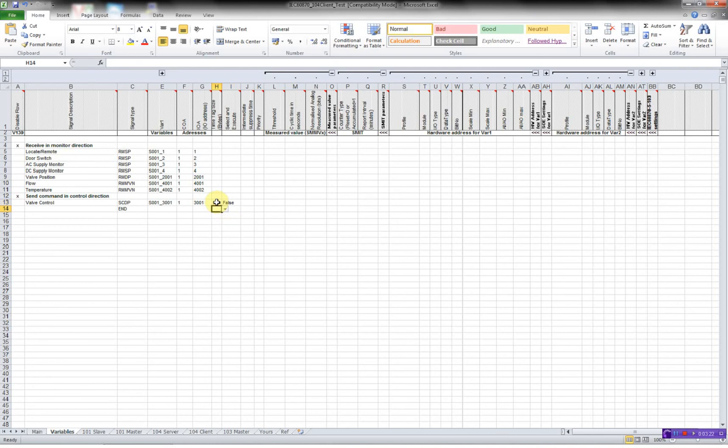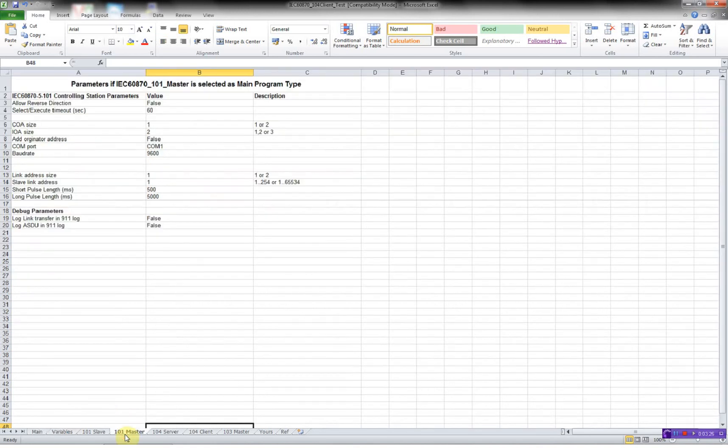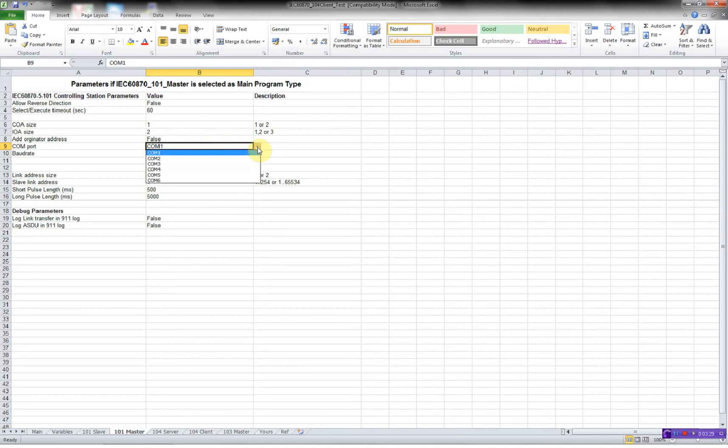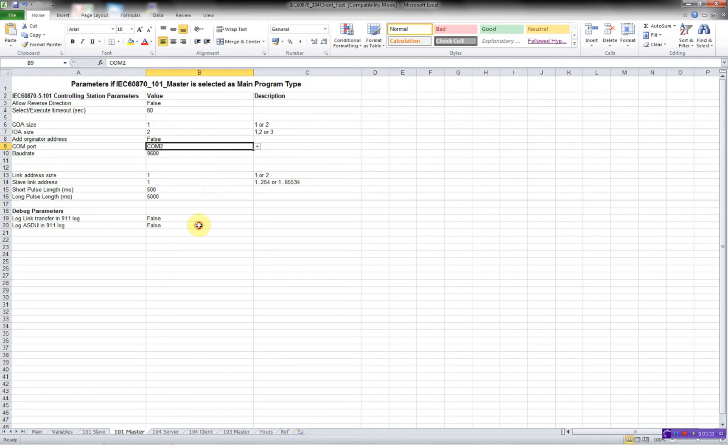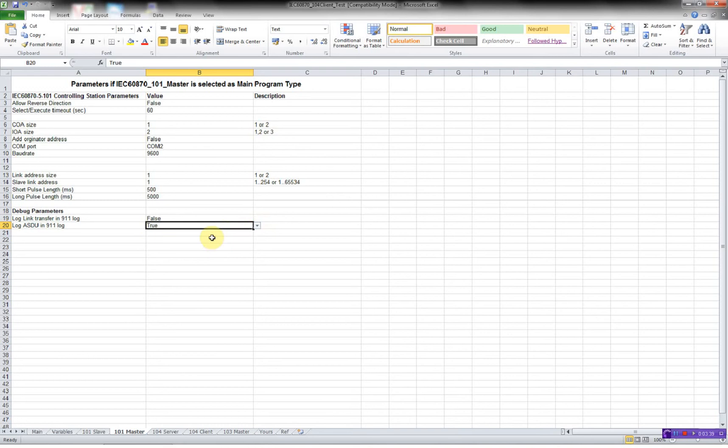Now we have done all the variables configuration. We'll move on to the 101 master. Here I'll specify what COM port we are using. In this case we are using COM port 2. I'll enable the logging of all ASDU sent to the RTU32 so we can use Telnet or our event viewer.